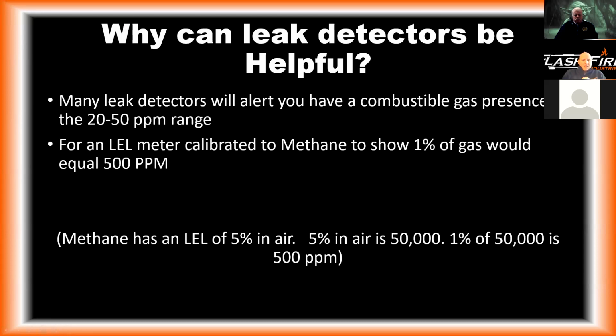Suffice to say, all I'm trying to explain to you is that when our leak detector can detect 20 to 50 parts per million of gas, for our LEL sensor to show 1% of gas would be 10 times that. So we're going to get a much lower detection rate with those leak detectors, or potentially our PID meter, than we will by using that LEL meter. Okay.